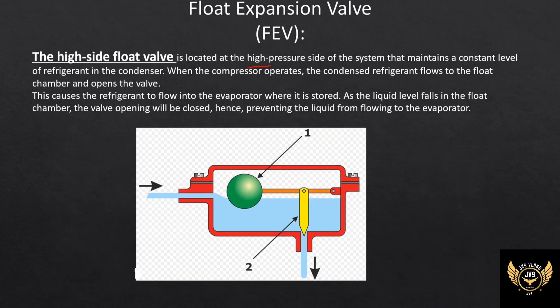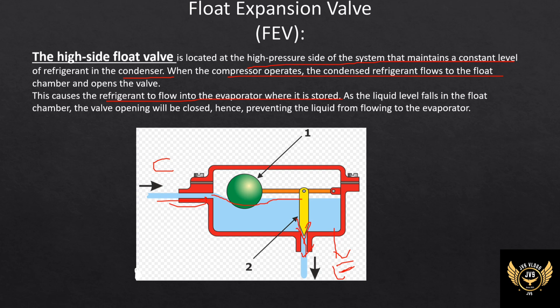The high side float valve maintains the refrigerant level in the condenser. The condenser maintains a constant level of liquid refrigerant. When the level increases, the valve opens to release refrigerant through the pipe, and the amount of refrigerant flow is regulated accordingly. The float valve will close when the level is restored.